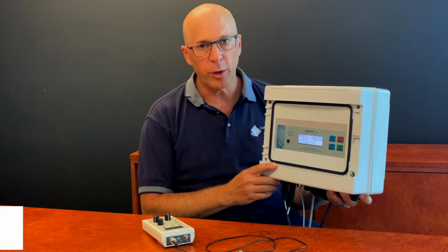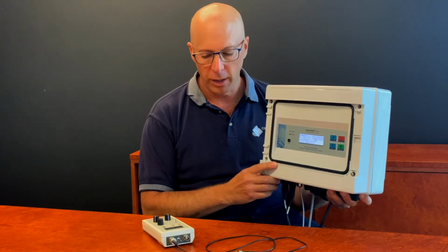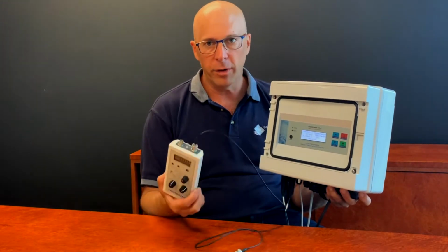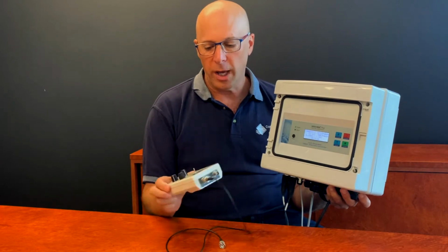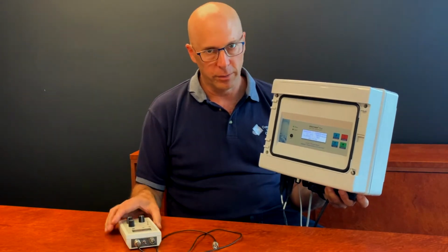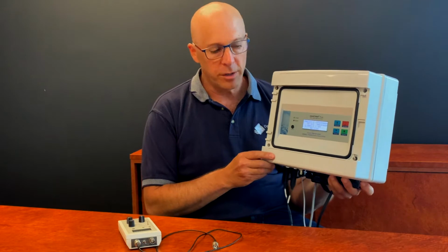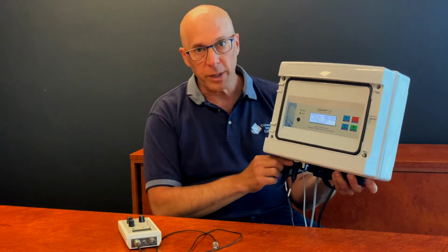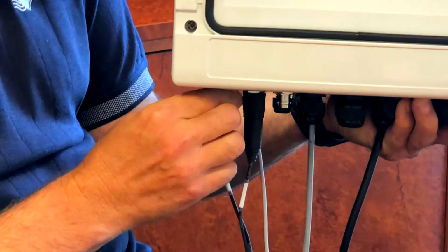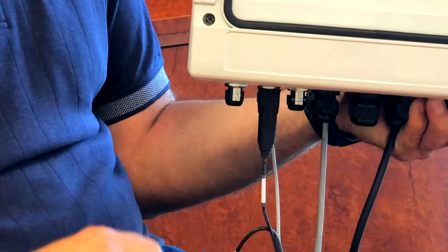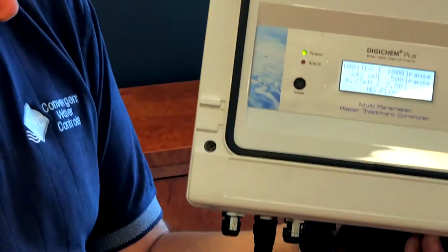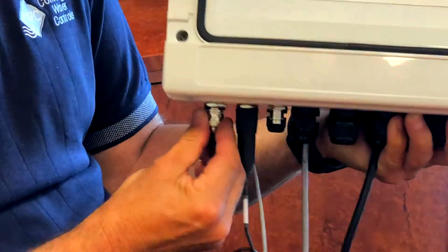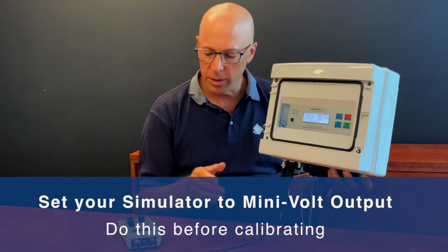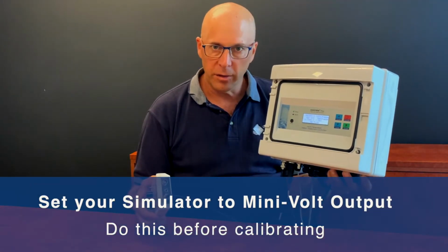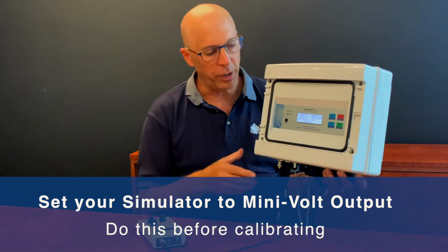Today I'm going to explain to you how to calibrate the ORP on a DIGICHEM Plus controller using a millivolt simulator which outputs a known millivolt. So the first step is to disconnect the ORP sensor from the controller, which is the BNC connector here, and then plug in the cable from the simulator into the ORP input. However, before doing this, one needs to set the simulator to millivolt output, which I've pre-set.